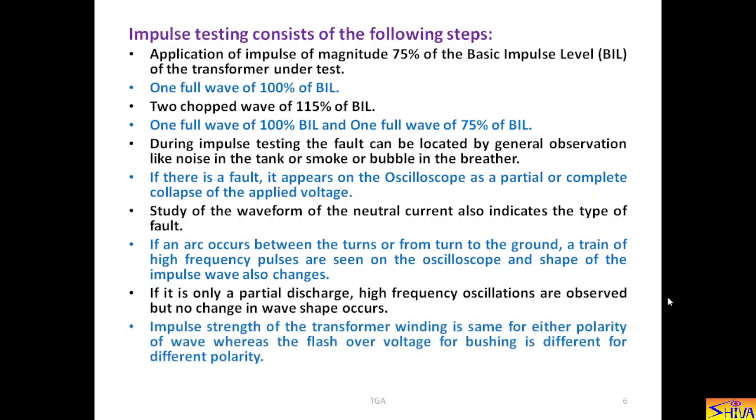Impulse strength of the transformer winding is same for either polarity of wave whereas the flashover voltage for bushing is different for different polarity. That is all about the high voltage testing of the transformer.